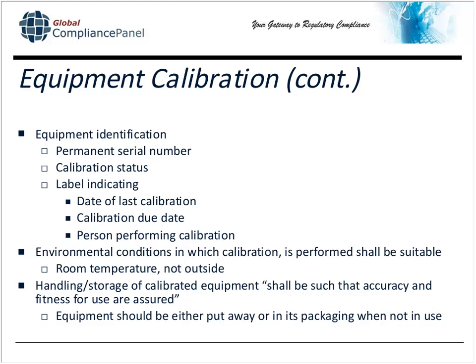You also want to identify calibration status. It's usually on a sticker, usually a green sticker I've seen, and the label on the sticker, in addition to the calibration status, has the date of calibration, the calibration due date, and the person who performed the calibration. Initials are fine. There's no need for a formal signature.